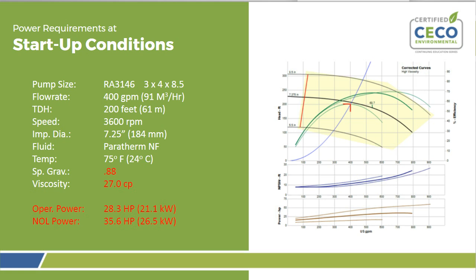This being the case, your 25 horsepower motor that you had spec'd out to cover your operating conditions will probably blow all the fuses and all the circuit breakers in your switchgear to start the pump up. It will overload before it ever gets up to temperature.